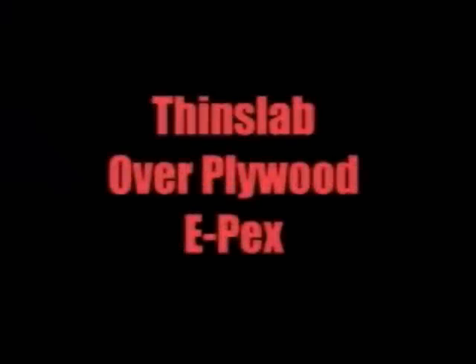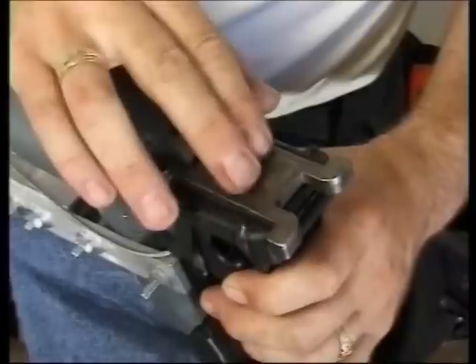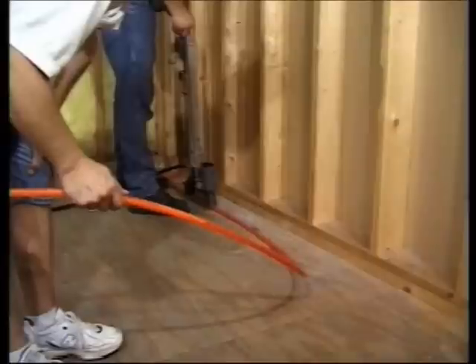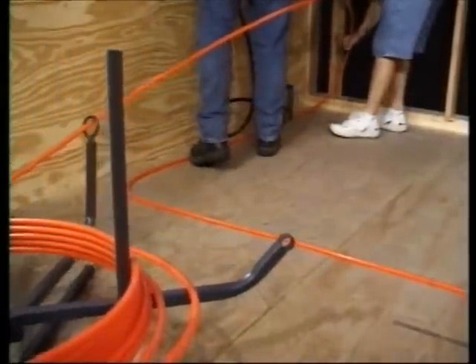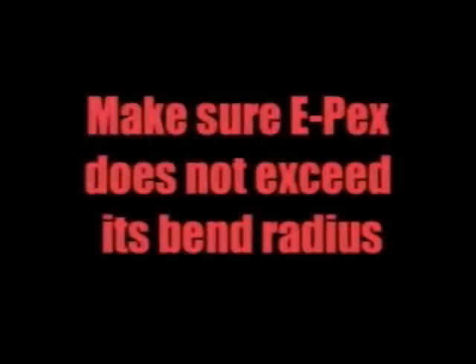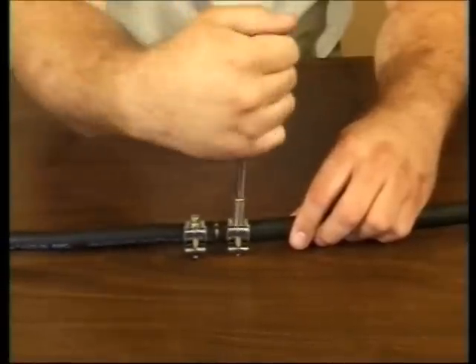Epex in a thin slab installs in a single serpentine pattern. Place a coil of Epex on the unwinder and temporarily secure one end near the manifold. Use the PEX head on the staple gun and the extension arm to secure the tubing every 8 to 12 inches. Go to within 6 inches of the perimeter and work back to the manifold or toward the center of the zone. If bending is required, make sure the Epex does not exceed its proper bend radius. If your tubing is damaged during installation, follow the instructions in the field repair kits.